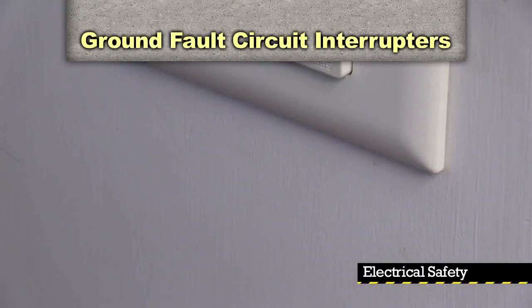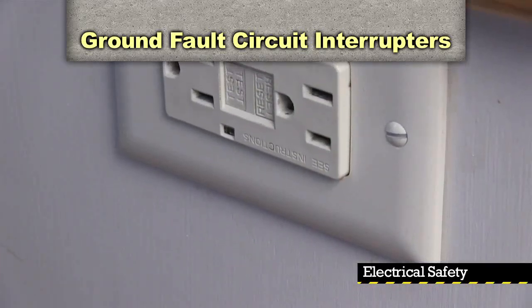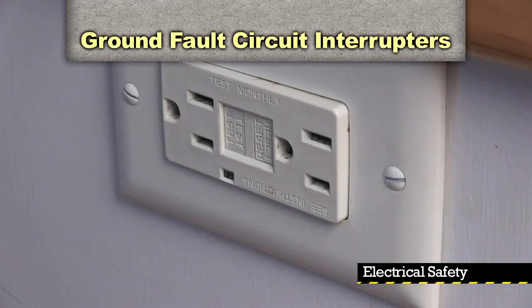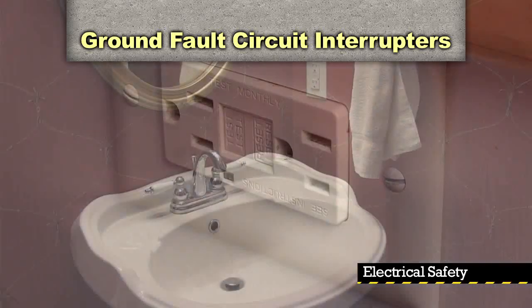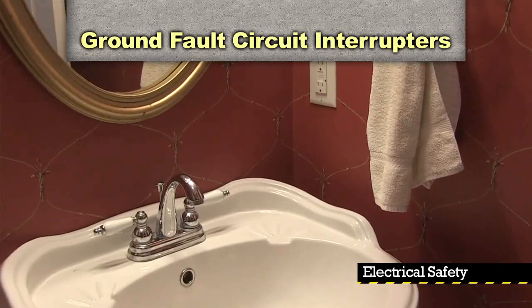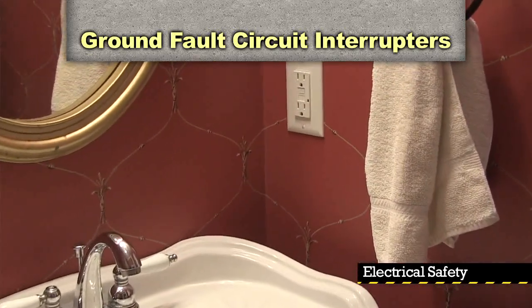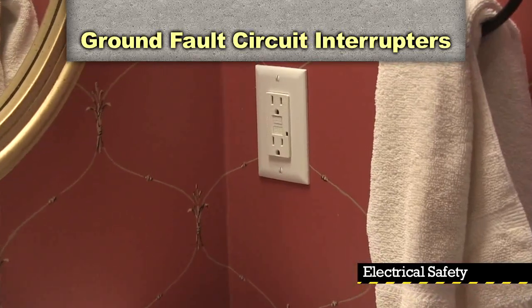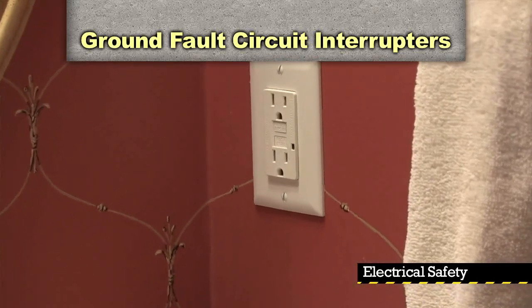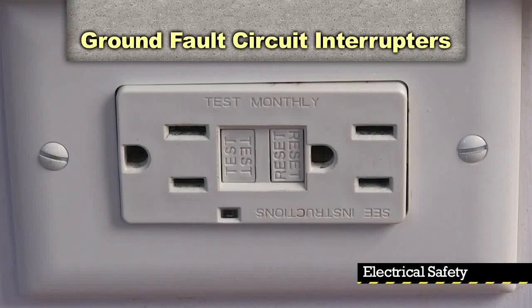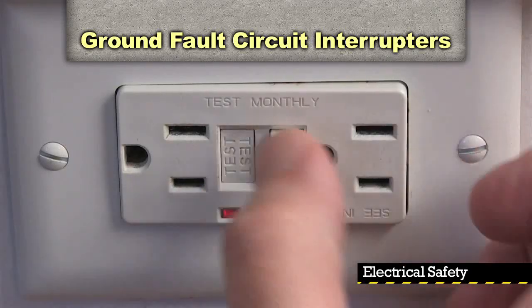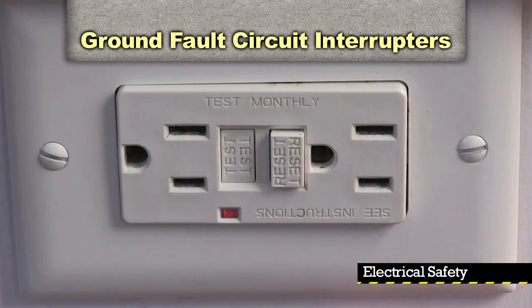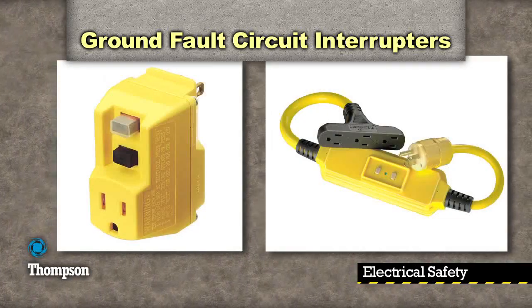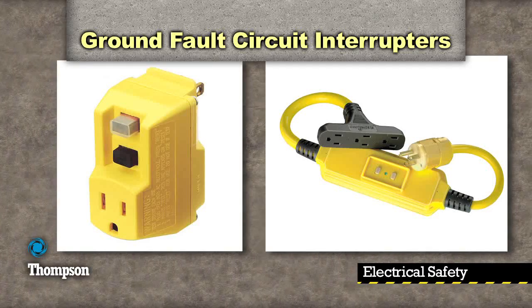Ground fault circuit interrupters, or GFCIs, reduce the likelihood of fatal shocks by automatically switching off the power when a small amount of earth or grounded current is detected. GFCI receptacles might be found in homes or hotels, in the bathroom or kitchen, where an electric appliance such as a hairdryer or toaster has a chance to fall into a sink full of water. If this occurred, the GFCI would automatically shut off the power to the receptacle. The receptacle would have to be manually reset. GFCIs can also be portable and used with extension cords and power tools.